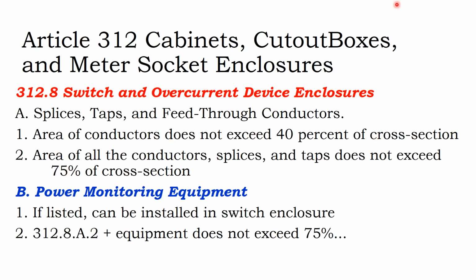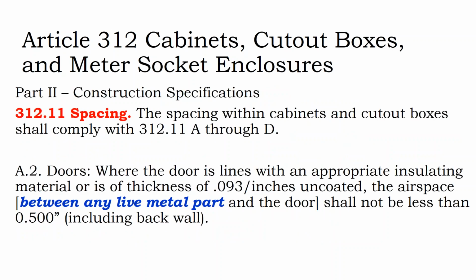So in my designs that I get on my line side tap connectors, I look at my conductors going into a supply side tap, and I think, well, if I have 4 2-inch conduits, that could go into a 12-inch box. But it may be that the conductors in the box, the fittings, can only accommodate no more than 75%. And so if I have 8 inches of conduit going into a 10-inch box, that would be greater than 75%. I'd have to go the next step up. So sometimes you can accidentally undersize your boxes because you're just plugging in a lot of stuff into that box. So that's something to take a look at.